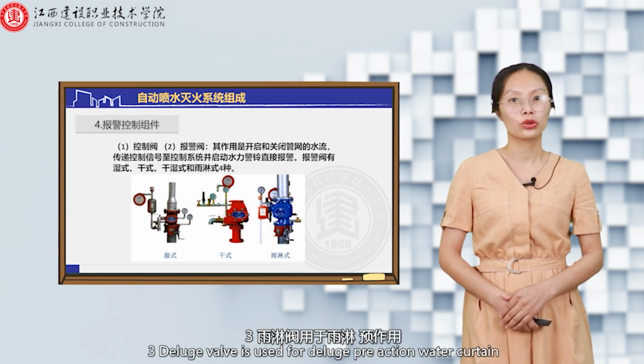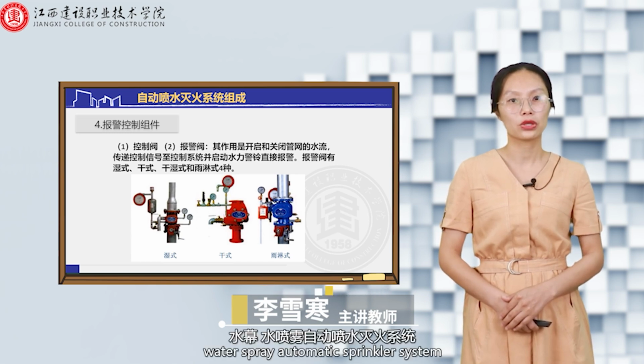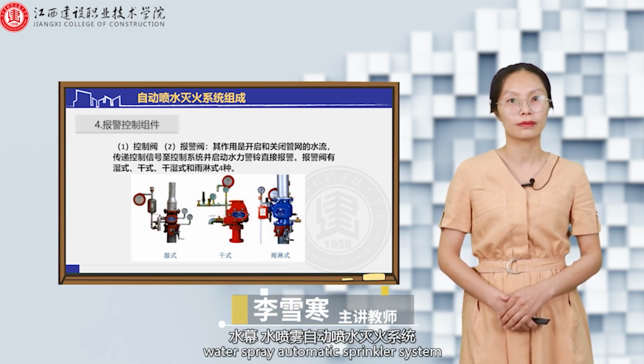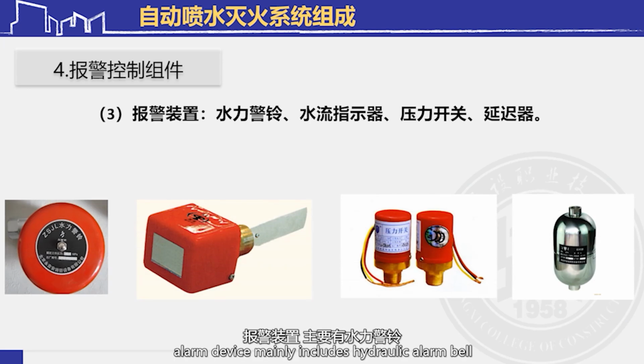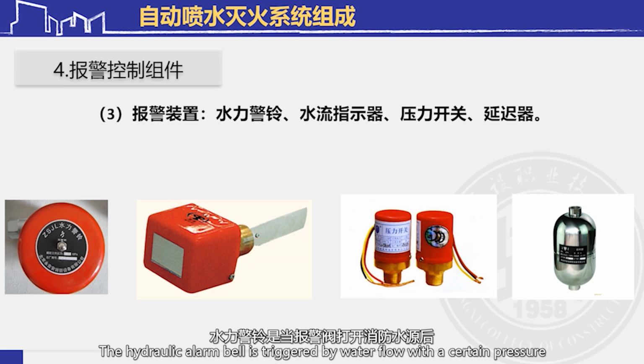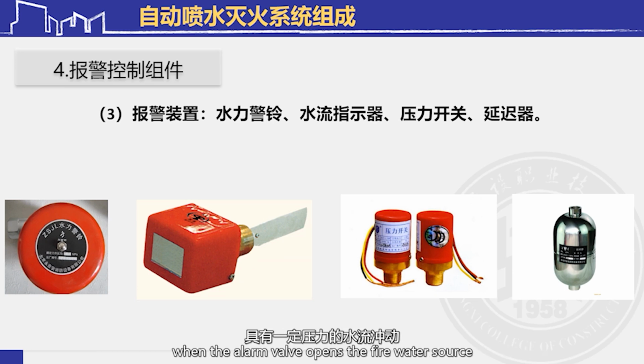Third, deluge valve is used for deluge, pre-action, water curtain, water spray automatic sprinkler system. Alarm device mainly includes hydraulic alarm bell, water flow indicator, pressure switch, and delay device. The hydraulic alarm bell is triggered by water flow with a certain pressure when the alarm valve opens the fire water source, causing the impeller to ring the bell and sound an alarm.